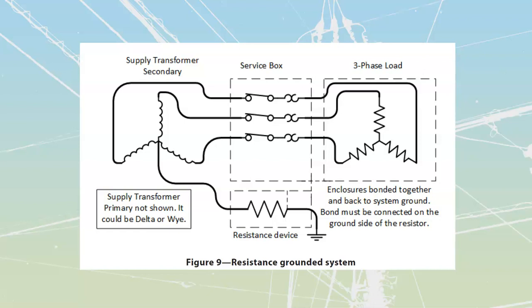However, the impedances we use to slow down the flow of current are usually resistance or inductance. We don't want to use a lot of capacitance, because if we've got something capacitive and go into a leading power factor, we can raise the system voltage—our transformer voltages themselves will actually increase. This would make any fault you have more dangerous, so rather than making a fault more dangerous, we just don't use capacitive systems by and large. There are a couple of small specialized applications where capacitance is sometimes used, but they're so specialized and rare that we're going to leave them out entirely in our study of impedance grounding.